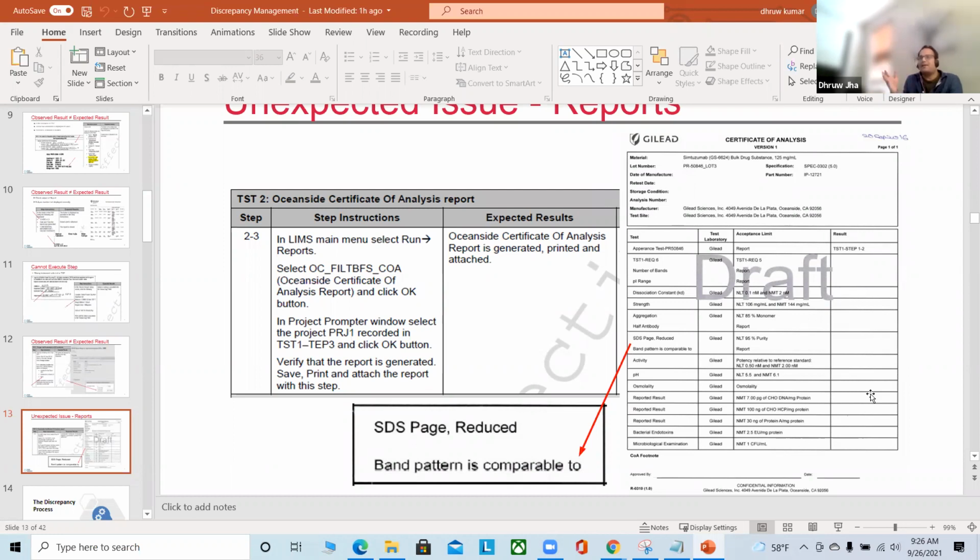Remember what I said when I was reviewing your document, IQ, OQ. You wrote the first version. Once I gave you comments, whatever you're changing in your document, make it version 2. Am I right? That's how it works in the real world. So I wanted you guys to follow that so you understand how those things work.